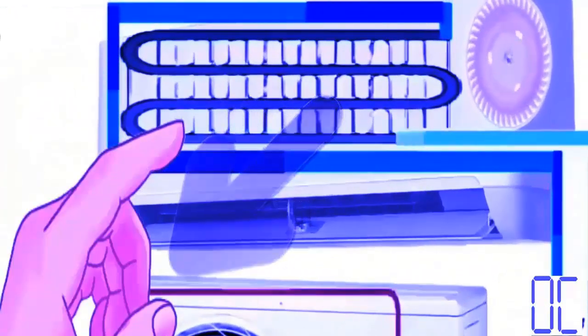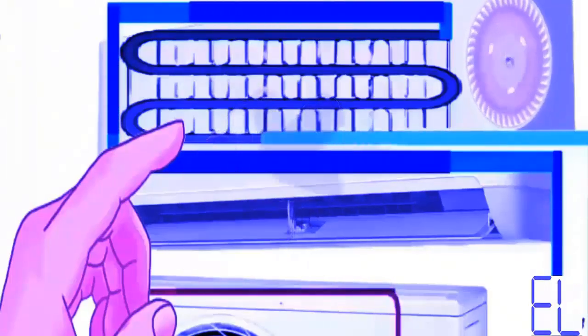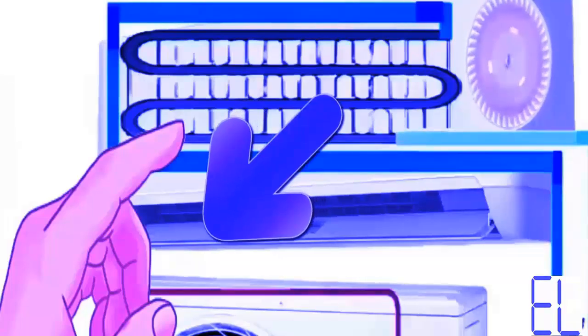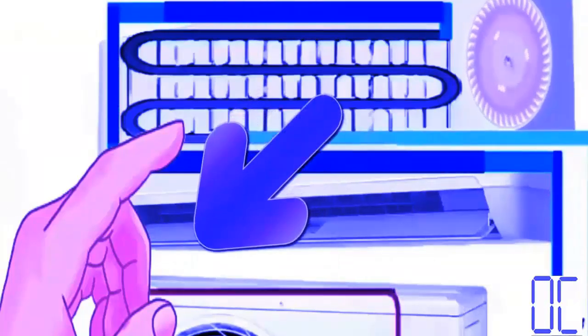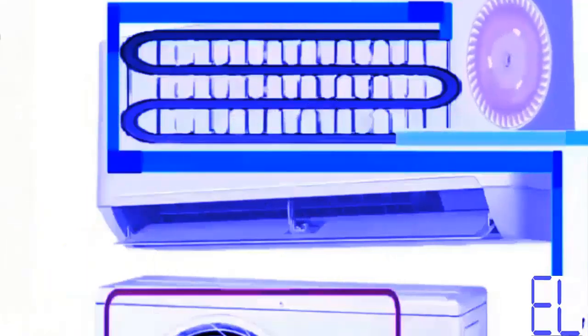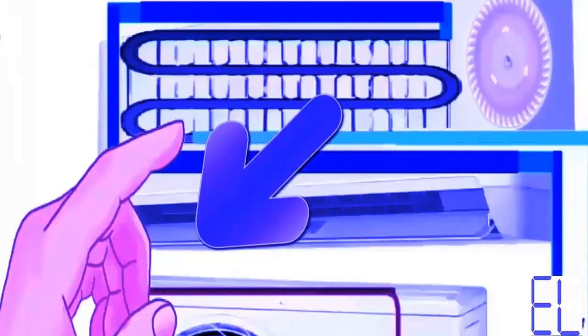2. If the error continues, with the unit turned on, check in cooling mode if the air supplied by the indoor unit is sufficiently cold. Place your hands in front of the indoor air outlet to feel the temperature. 3. If the air is sufficiently cold, there is probably no refrigerant gas leak, and the problem could be a false alarm.